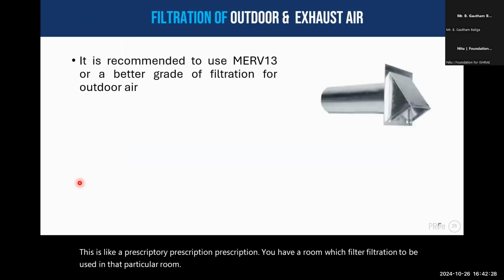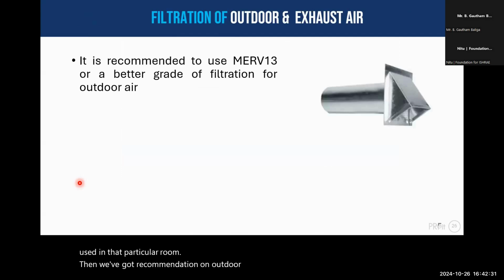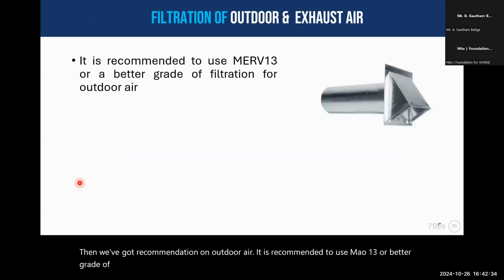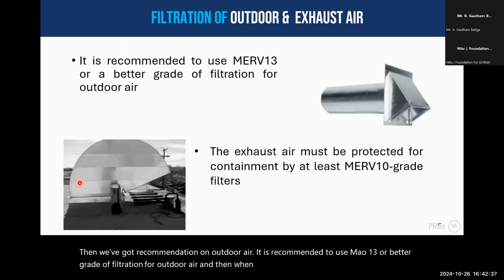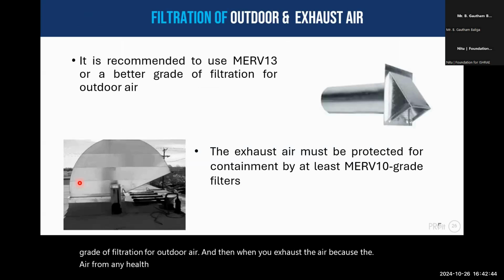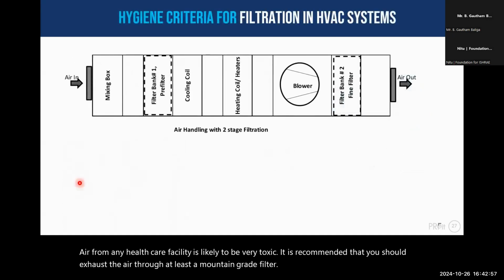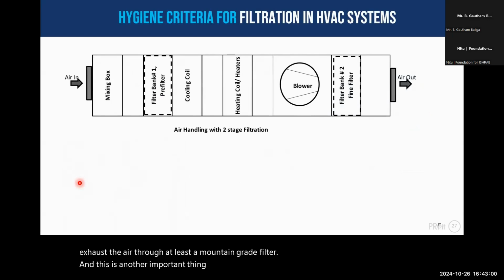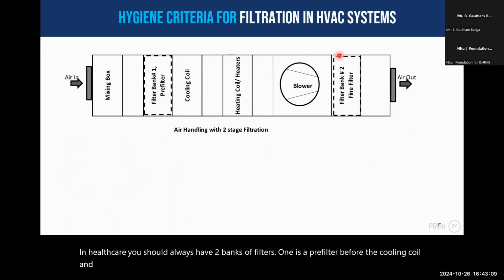Then we have got a recommendation on outdoor air. It is recommended to use MERV 13 or better grade of filtration for outdoor air. And then when you exhaust the air, because the air from any healthcare facility is likely to be very toxic, it is recommended that you should exhaust the air through at least a MERV 10 grade filter. And this is another important thing about any filtration in healthcare. You should always have two banks of filters. One is a pre-filter before the cooling coil, and then there should be a fine filter after the blower.